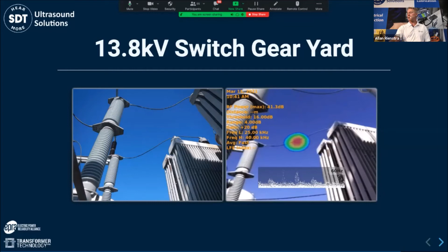What you see here is a bar graph called PRPD, an acronym for phase resolved partial discharge. This allows us to analyze the source of the corona at 360 degrees, across all phases of the sine wave. By looking at the patterns through those 360 degrees, we can determine whether it's a surface discharge, a floating discharge, or corona or some other effect. This is a new analysis tool that we have.